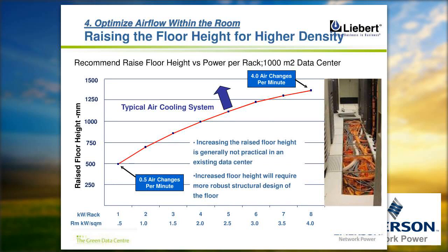Okay, my next slide talks about the recommended false floor height depending upon the rack kilowatt. For anywhere around 3 to 4 kilowatt, you can use about 700 to 1000 mm, and if density is more, it can go as high as almost 1.2 meter also. There are some data centers in India which are built with more than 1000 mm false floor height. But then the overall height of the floor or building has to be considered properly right at the building construction level.